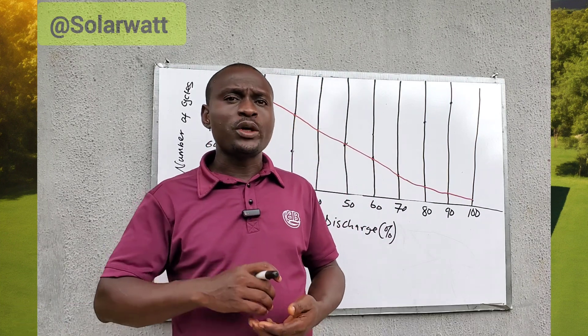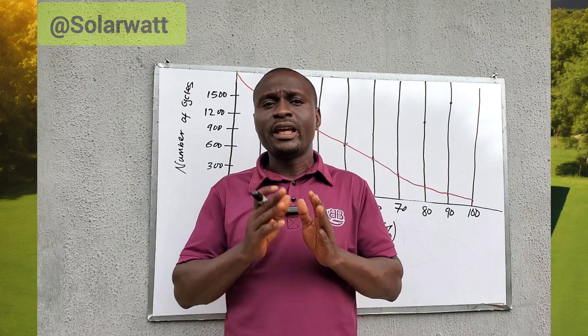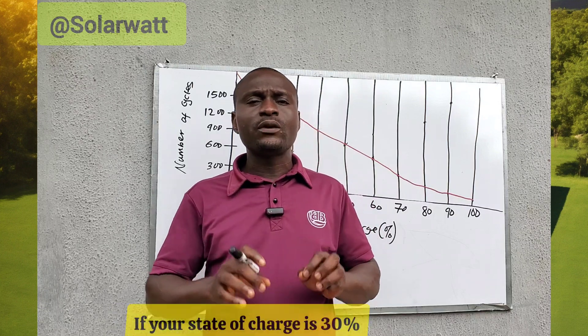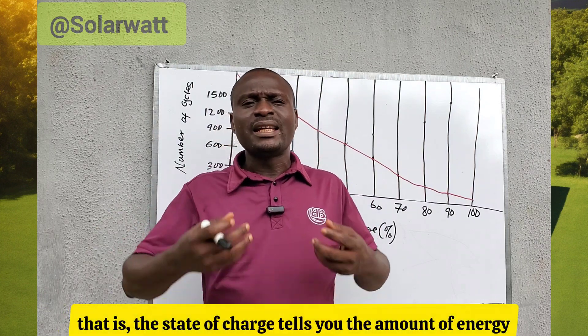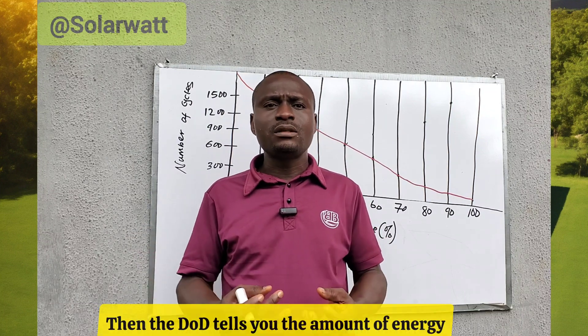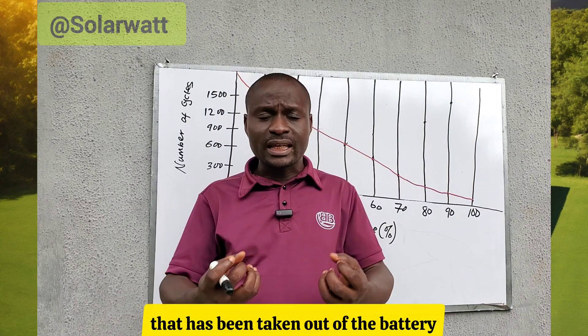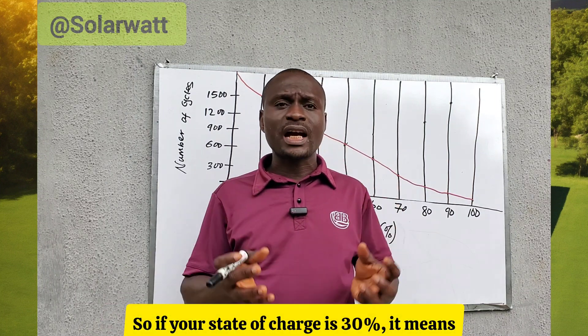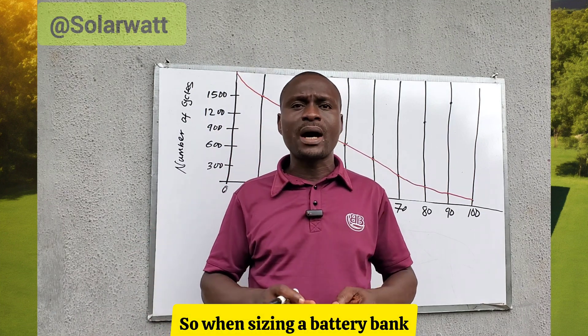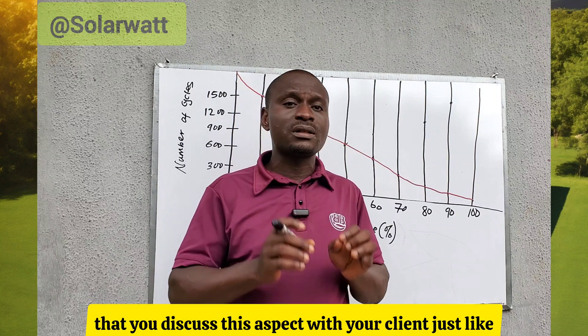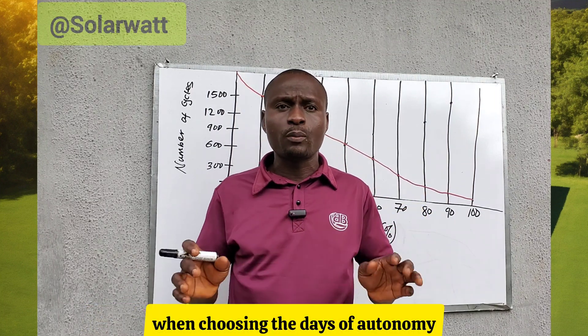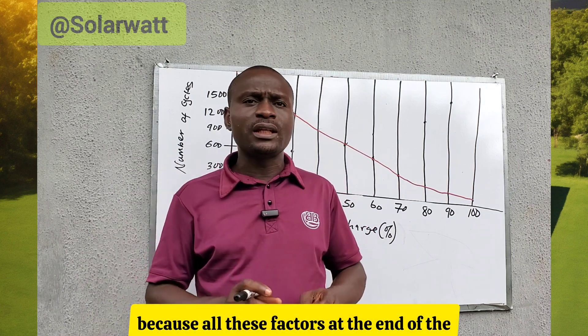DoD and SoC are both represented in percentage. If your state of charge is 50%, it means your depth of discharge — what has been drawn from the battery — is also 50%. The SoC tells you the energy remaining in the battery; the DoD tells you the energy taken out. So if your SoC is 30%, your DoD is 70%. When sizing a battery bank, it is very important that you discuss this with your client.